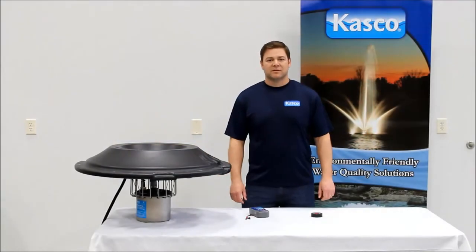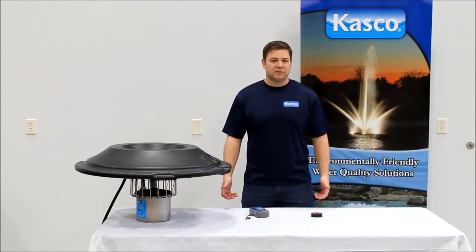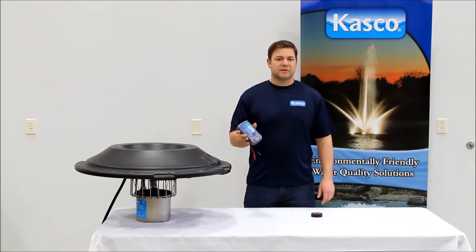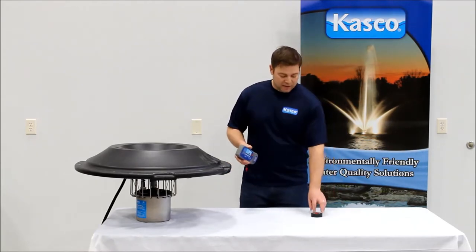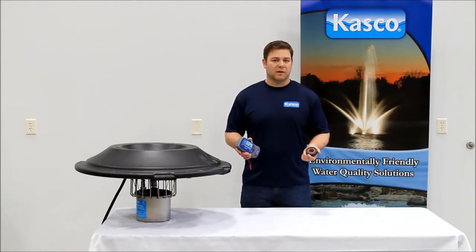Hi, I'm Joe Holtz with Kasco Marine and today we're going to go through how to properly troubleshoot and diagnose one of the more common field issues, which would be a GFI or GFCI trip. For proper troubleshooting you're going to need a couple tools: first is going to be the megohmmeter, and next you're going to want some electrical tape or duct tape, something to cover the photo eye if you're using a 120 volt C25 control panel.